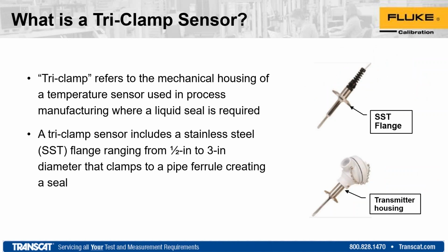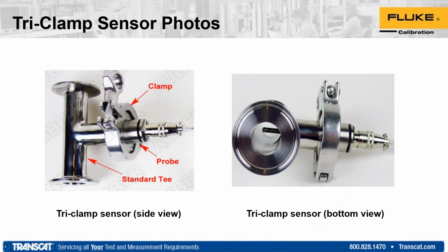So I keep referring back to TriClamp, sanitary sensors, or Clover. What that means is it's just the design of it, so we're going to touch on that briefly. Basically, the TriClamp sensors are the ones with these little flanges. The flanges can range in size from a 1/2 inch up to as big as 3 inches. The reason it's "tri" is there are 3 parts: usually the inlet, the clamp, and then the actual sensor. So, the 3 pieces, hence TriClamp. I've also seen these called Clover, and then sanitary sensors. So, just digging in a little bit on the explanation of some of the terminology that I'm throwing out there.